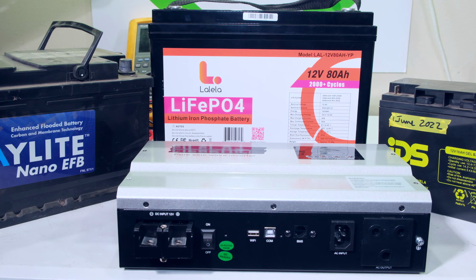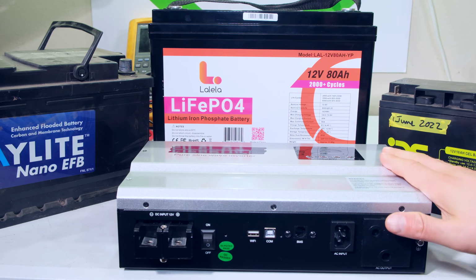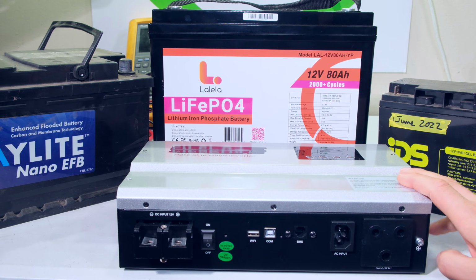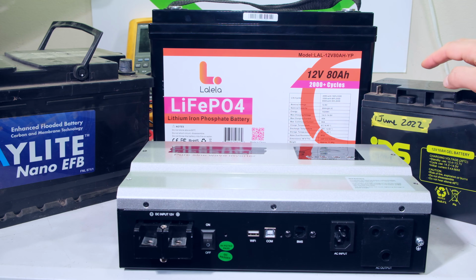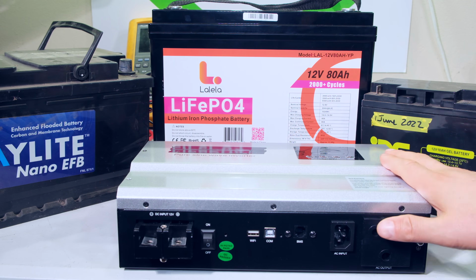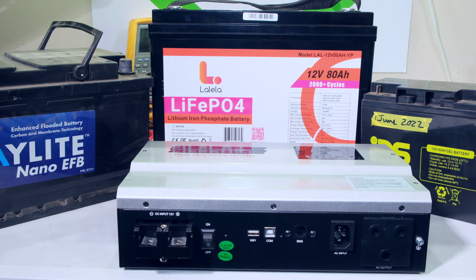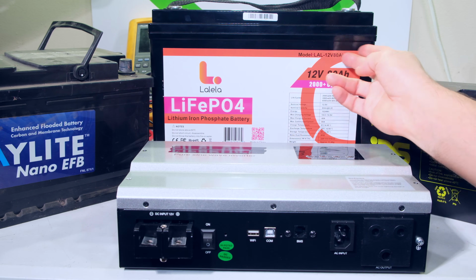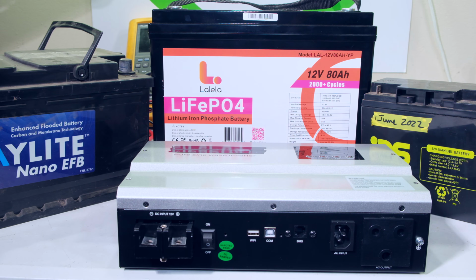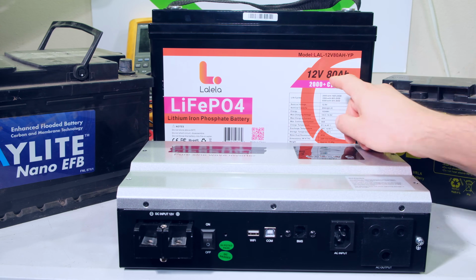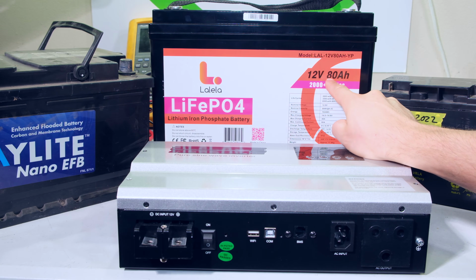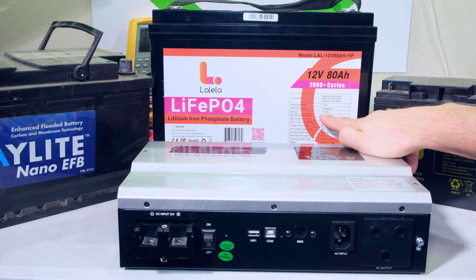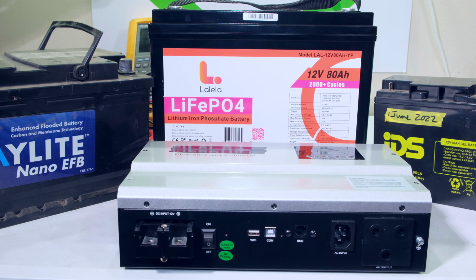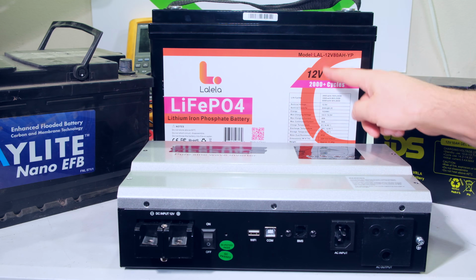Now, when selecting the battery, I also need to make sure that the battery can cater for the full load of the inverter. Now, this inverter's full load is 600 watts according to the faceplate specifications. If I had to use the smaller battery, this would be insufficient for a 600 watt load to be used for, say, maybe an hour or 2 hours. So I'm forced to use a battery with a much higher amp hour rating. And that is why I'm going to choose a bigger battery. So very briefly, if I want to see the capacity of this battery, it says 80 amp hours. So I can say 80 amps times 12 works out to be 960 watts. And actually on the sticker here, it says 1024 watt hours. That means I could squeeze out over 1 kilowatt for 1 hour with this battery.